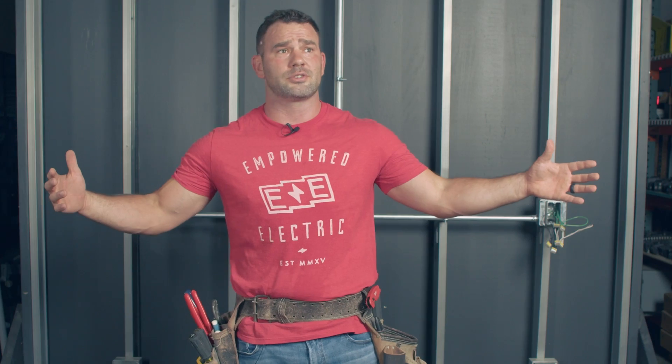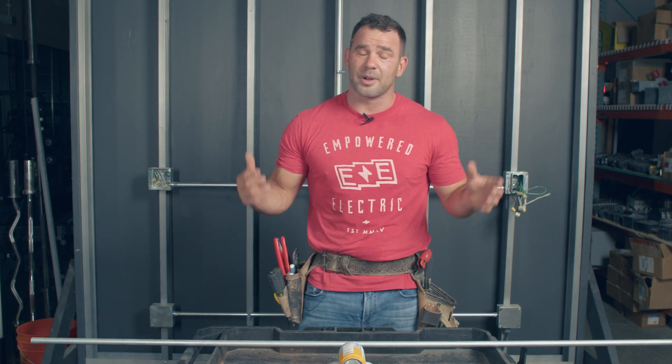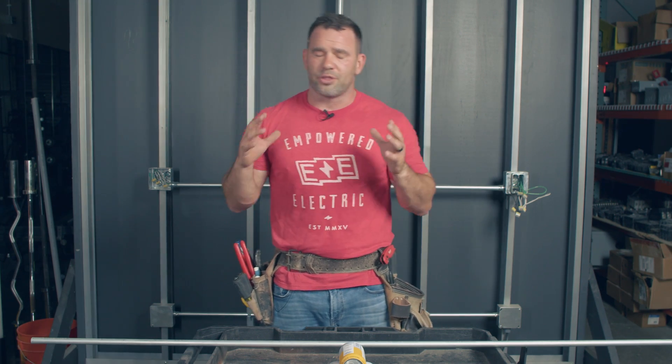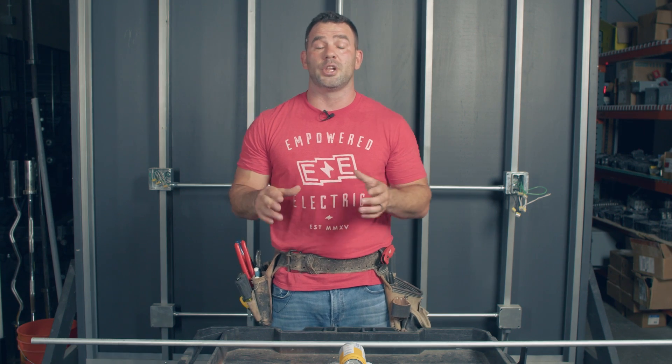We're over 800 subscribers — we hope this is making you more efficient. One of the things we talk a lot about is conduit. Today I'm going to talk about a three-point saddle. People love being able to do them, but listen: usually there's a better path — a 90 and a kick, an offset, a change in elevation. Don't let your mind go so quickly to a three-point saddle; they're not fun to pull through and they add up on bends really quick.